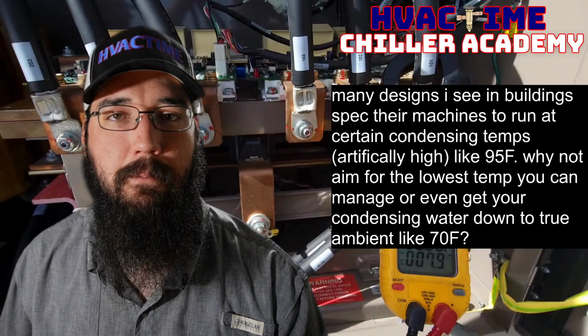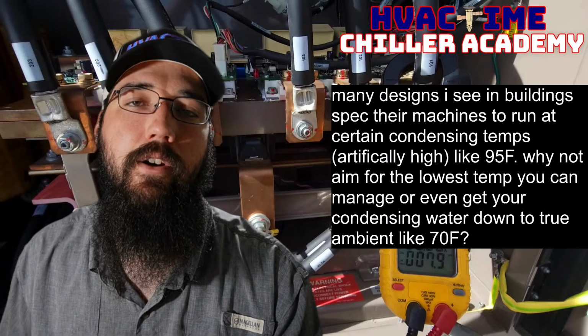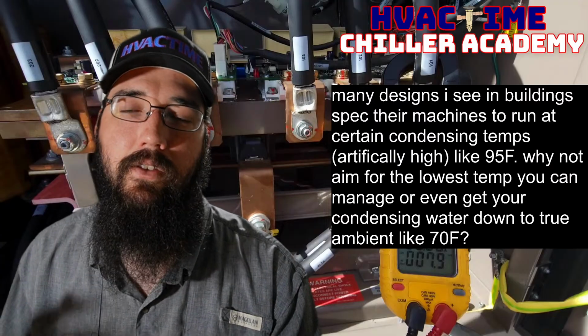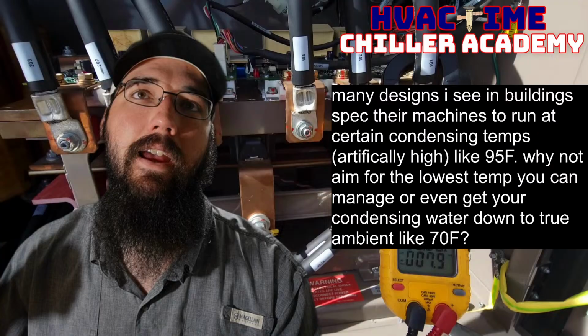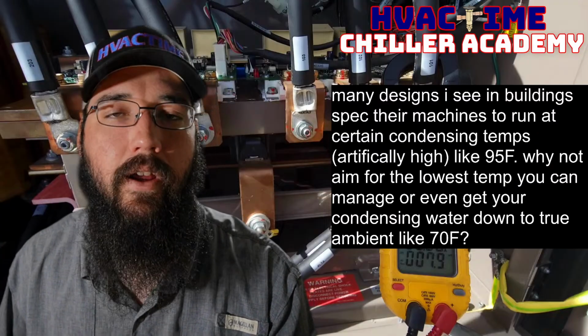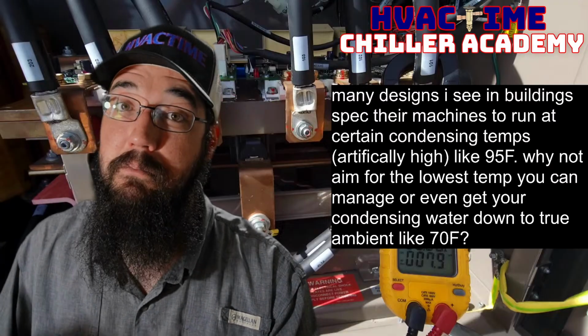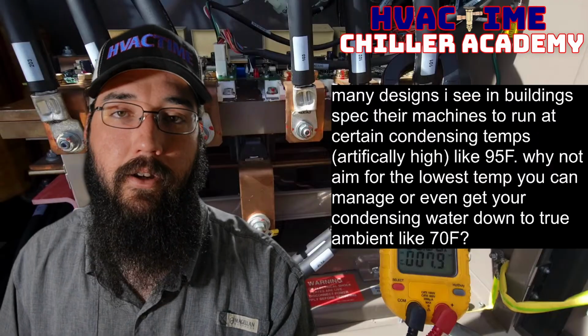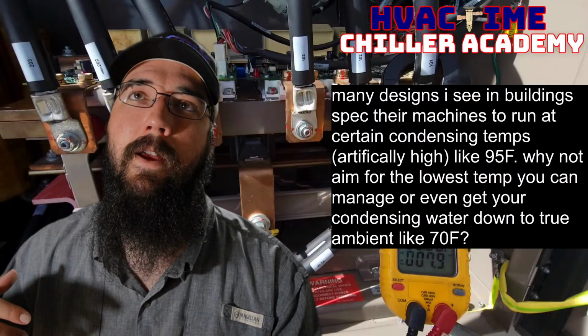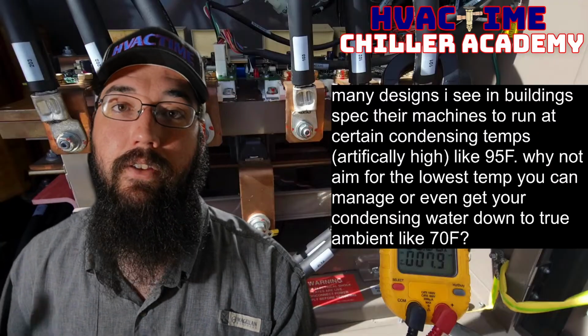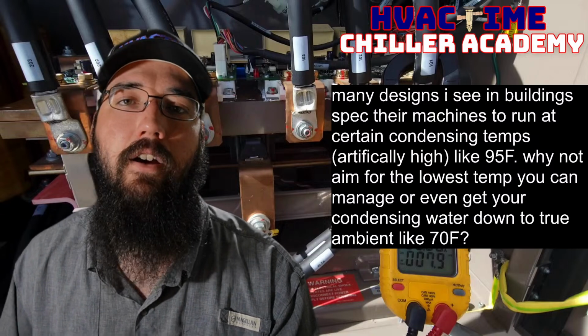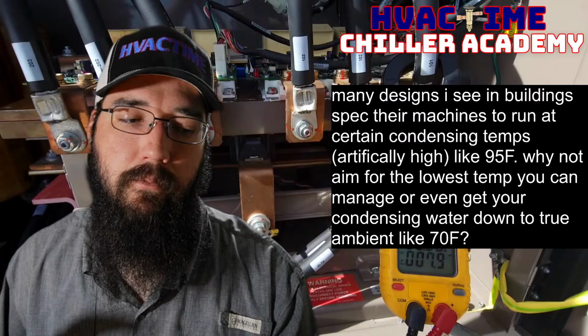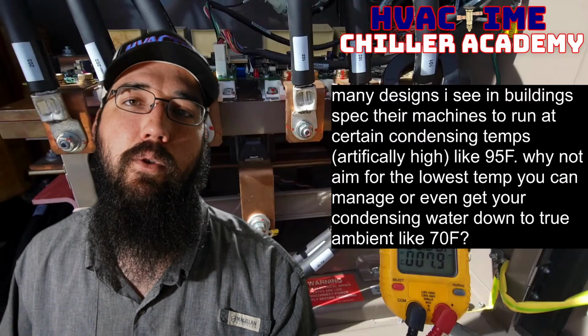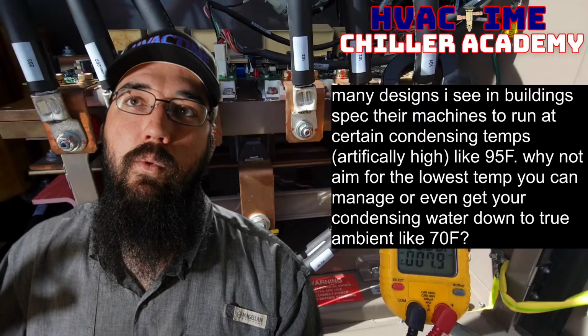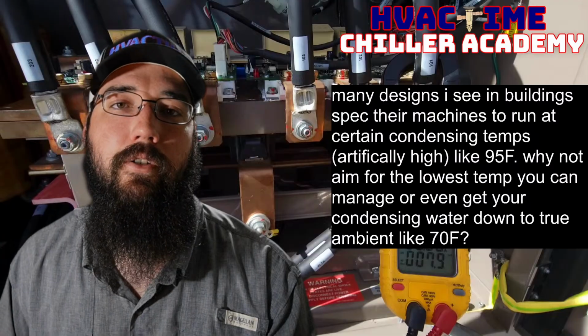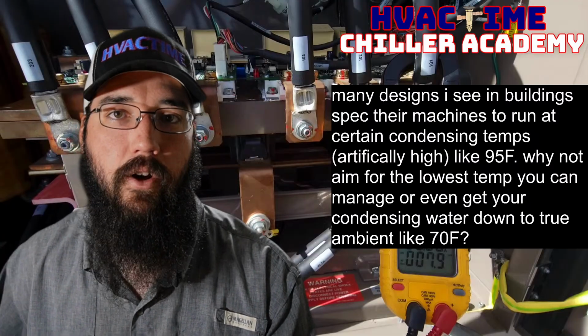What actual solution do I recommend? What is my go-to with that? Well, it is having a variable condenser water set point. To me, this is the perfect middle ground. And all it takes is a temperature sensor and a relative humidity sensor on the outdoors tied into the control systems. Most control systems nowadays, especially your regular PLCs, programmable logic controllers, so you're talking your Honeywells, your Distechs, your Johnson Controls, your Trane, all of these have basic control algorithms already built out for variable condenser water control. So once you have just the temperature sensors, it's not that hard to integrate the PID required to control this, the algorithm that we need.